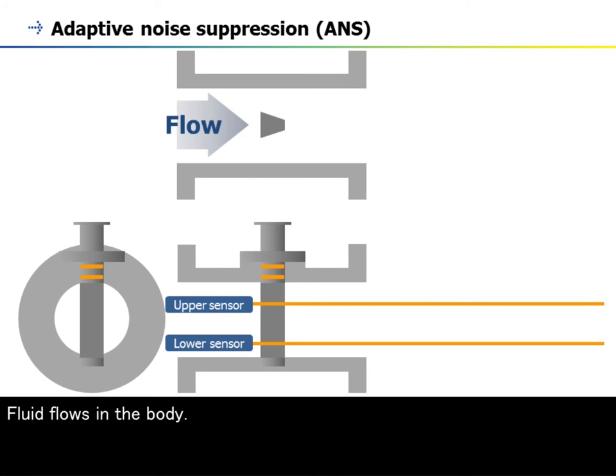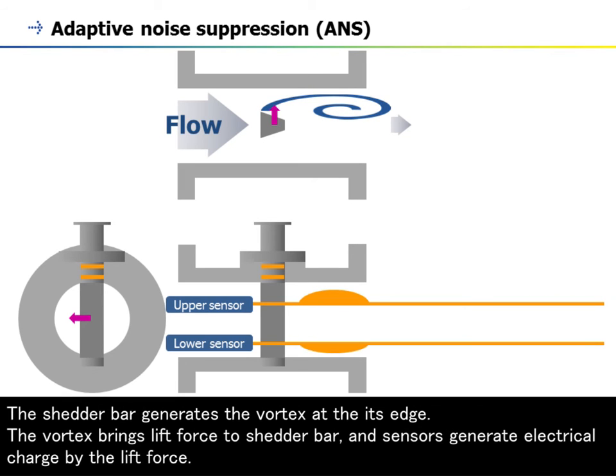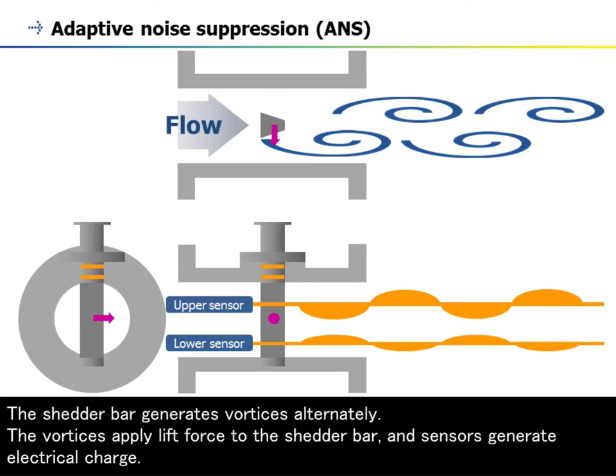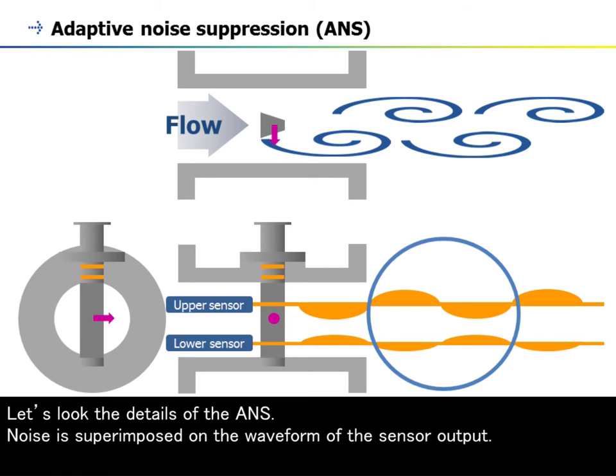Fluid flows in the body. The shedder bar generates the vortex at its edge. The vortex brings lift force to the shedder bar, and sensors generate electrical charge by the lift force. The shedder bar generates vortices alternately. The vortices apply lift force to the shedder bar, and sensors generate electrical charge. Let's look at the details of the ANS.